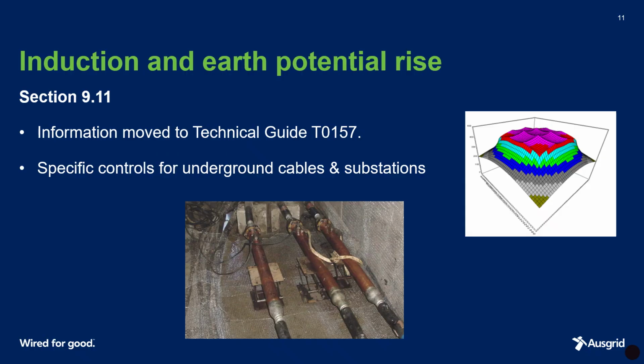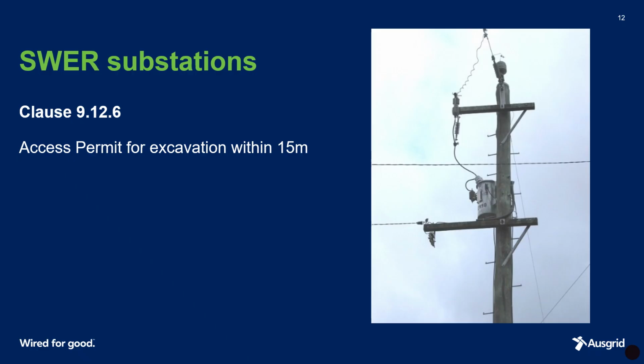The information about the hazards of induced voltages and earth potential rise has been moved from Section 9.11 to a new Technical Guide 157. As mentioned in the previous slide, there are changes to the controls to manage the risks of induction and earth potential rise for work on high voltage cables. In addition, the induction and earth potential rise controls required for work within substations have been more clearly set out. For single wire earth return or SWER systems, Clause 9.12.6 requires any excavation within 15 metres of a SWER substation to be carried out under an access permit. This aligns with the signage that is on all SWER substation poles.